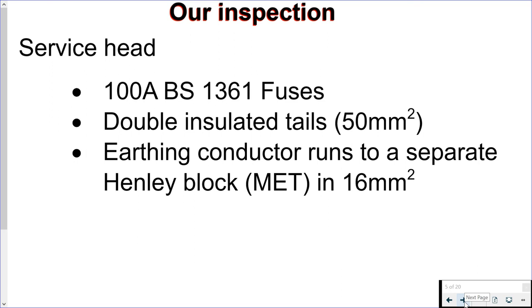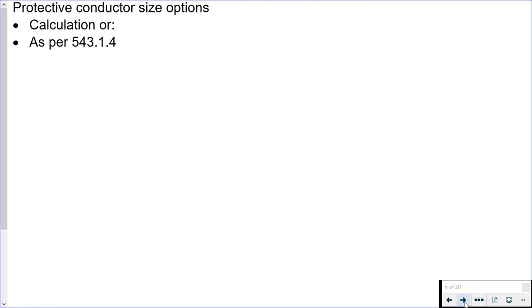We then have a look at the rest of our installation. It's a three phase system. We can see on the labeling on the service head that it is 100 ampere BS 1361 fuses. The cables coming from the service head into the meter and then back into our installation are 50 millimeter squared double insulated tails, and from the side of the service head we have an earthing conductor which is 16 millimeters squared.